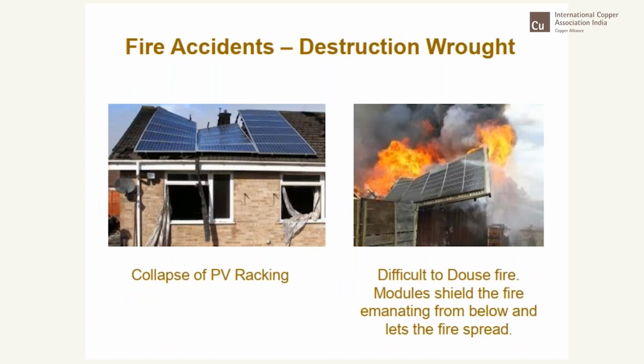As you see in this case on the left, you are seeing the collapse of the PV racking itself, because as was discussed earlier, the heat was so high that the metal below could give way. And if it happens to be a wooden roof, as in many Western nations, then you can very well understand what can happen. On the right, you see there is so little gap between the modules and the roof. You see the jet of water coming, but it is hitting the panel, which is actually shrouding the fire. So this is another issue.